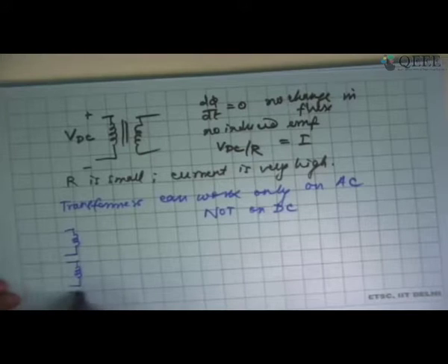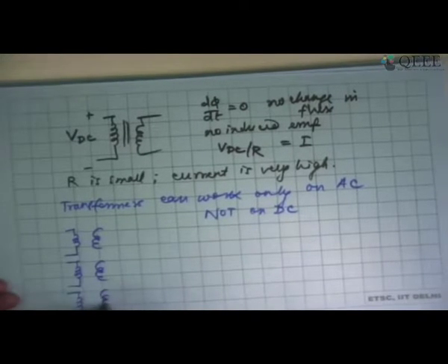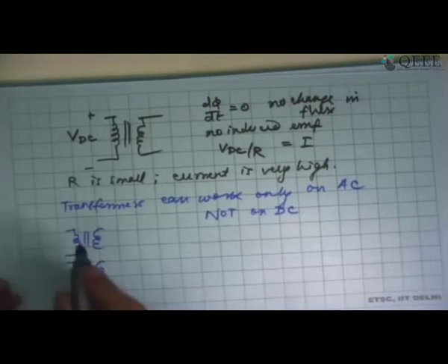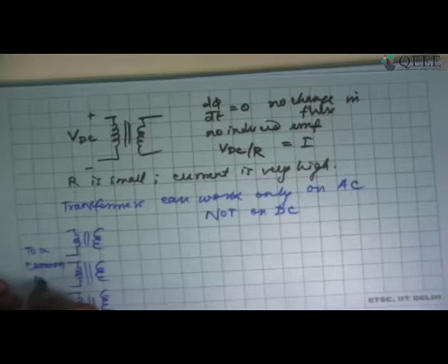The next question is, can we apply the concept of polarity test of a single phase transformer in the same way for a three phase transformer? Very much. If I have three single phase transformers and I want to connect them in star or delta, this is how I have to do it. First of all, I connect all of them to a common source.